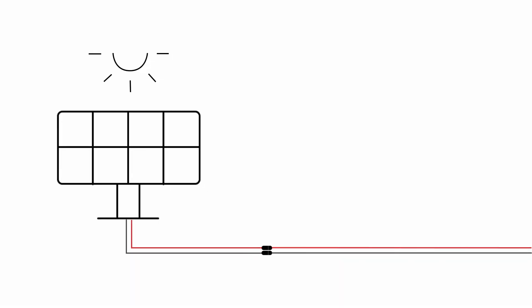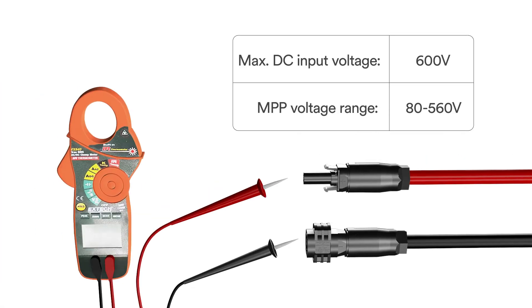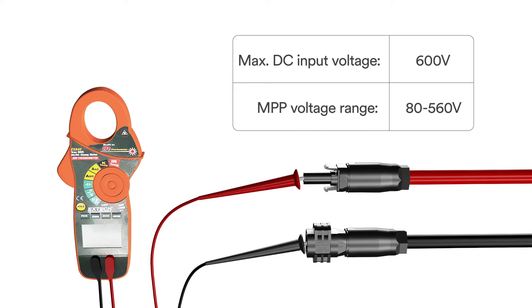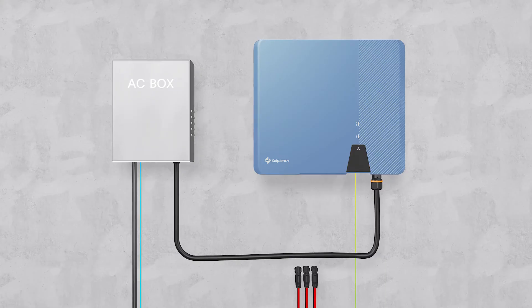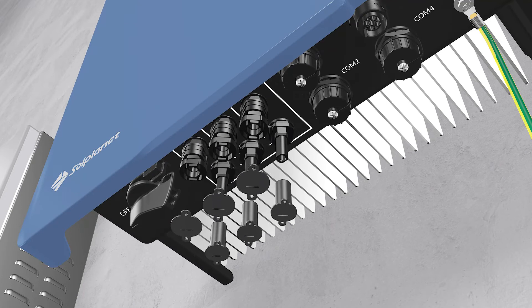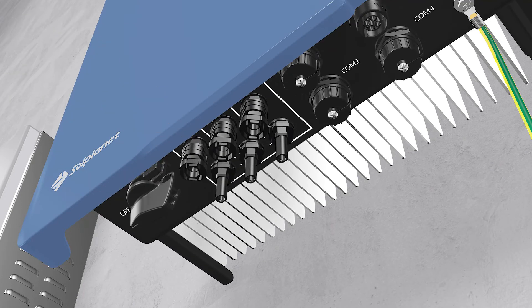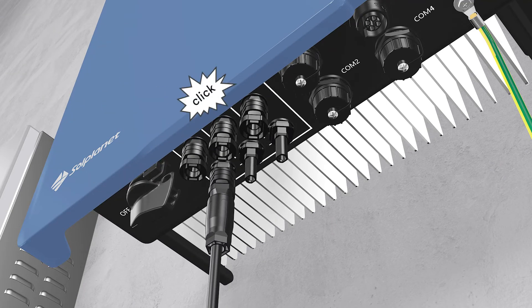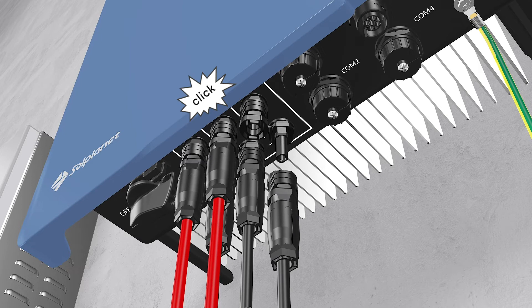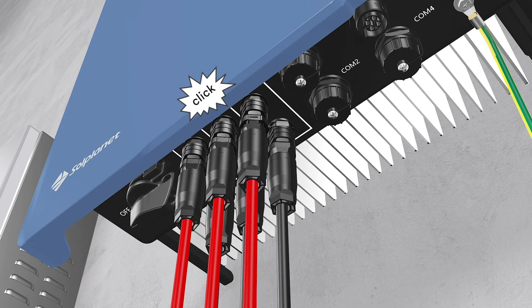Connecting the PV array, check whether the DC connector has the correct polarity. Ensure that the open circuit voltage of the PV array does not exceed the maximum DC input voltage of the inverter. Connect the assembled DC connectors to the inverter until they audibly snap into place. Ensure that all DC connectors are securely in place.